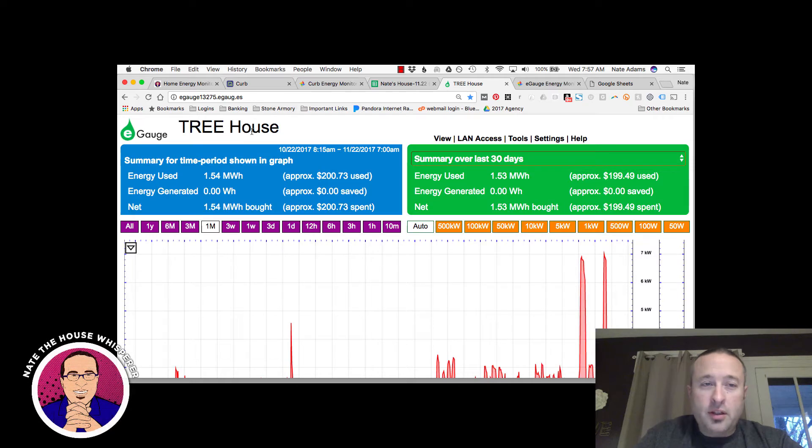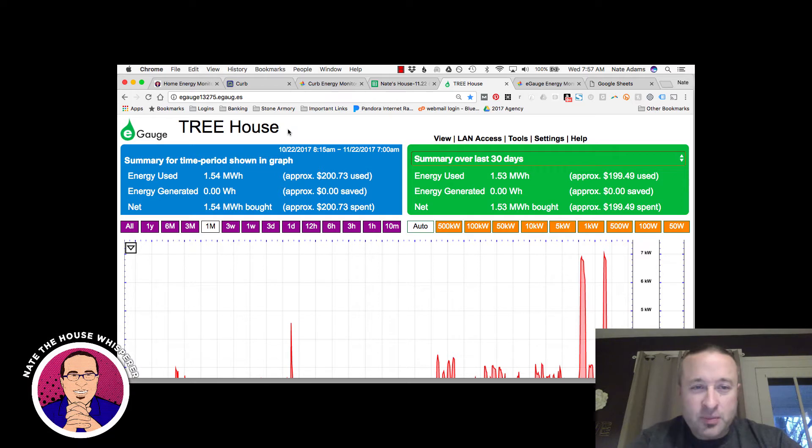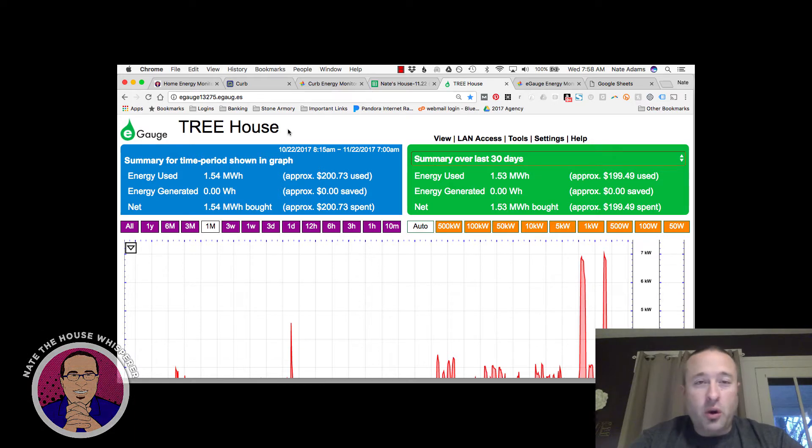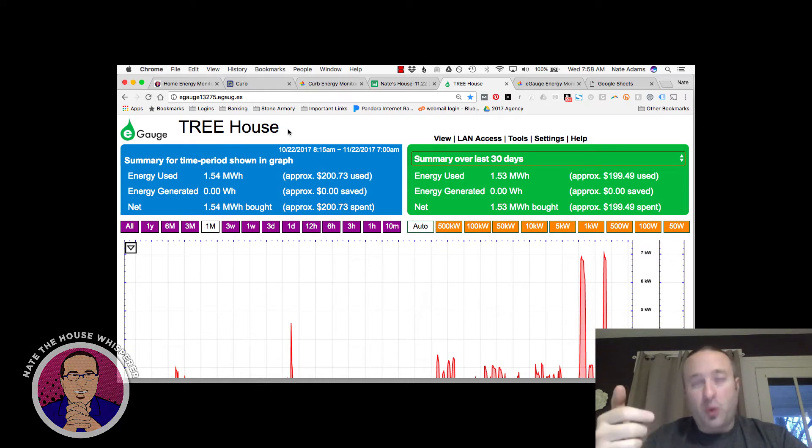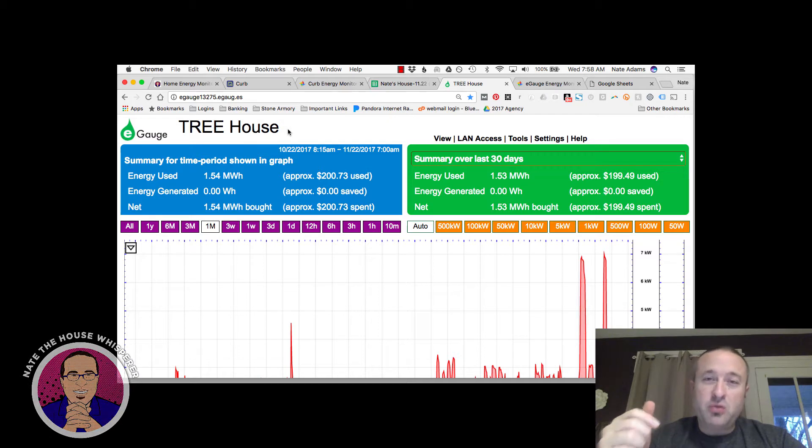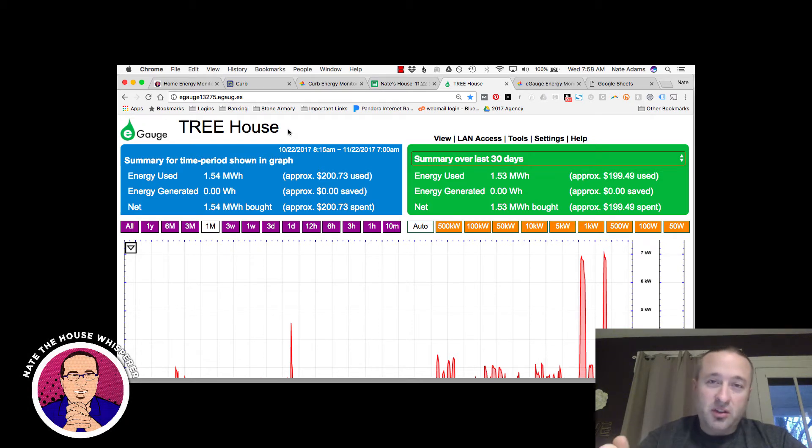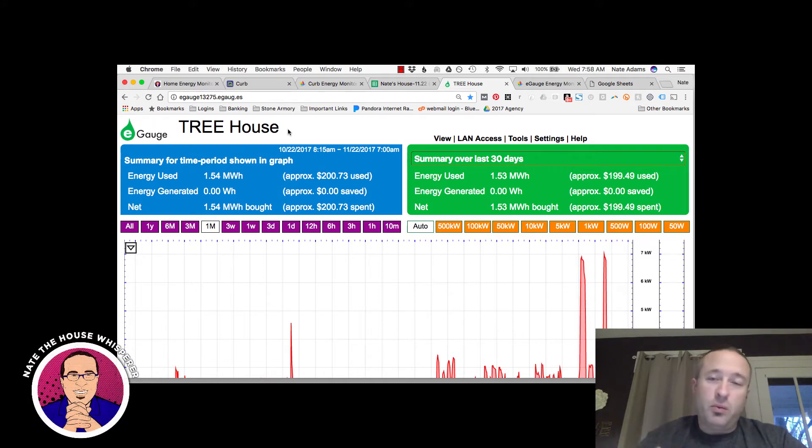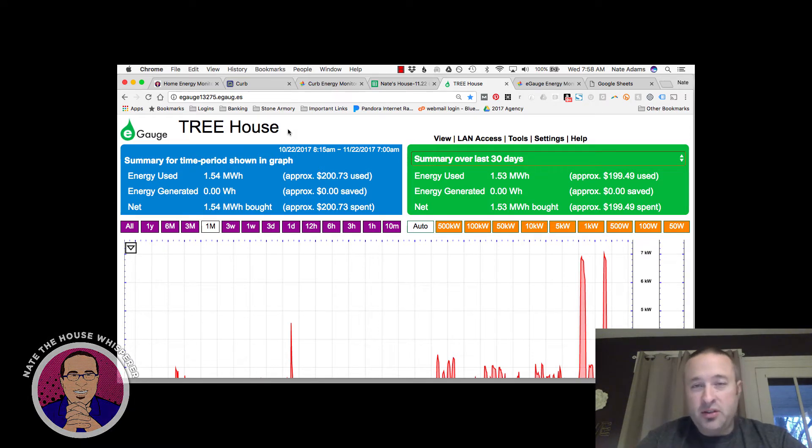So this is one project in particular. This is the Hiram College Treehouse, which was a deep energy retrofit that was done about three years ago now. And I've spent a lot of time in the building and played with it and learned this E-Gauge pretty well. So originally though, it was installed incorrectly. There were a bunch of clamps that were done backwards. So rather than showing that a circuit was using power, it was showing that it was producing power. And that actually made the information and the data from this utterly useless. So in May of 2016, I called E-Gauge and they were really helpful at getting that fixed up. And now the data is good coming out of the system, which is really nice to know.